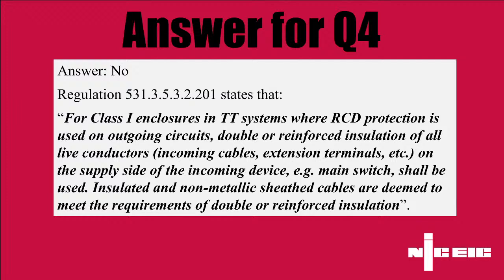And there is actually a note in that which does read: for class 1 enclosures in TT systems where RCD protection is used on outgoing circuits, double or reinforced insulation of all live conductors, the incoming cables, extension tails, etc. on the supply side of the incoming device, be it your main switch, etc., shall be used. Insulated and non-metallic sheathed cables are deemed to meet the requirements of double or reinforced insulation.